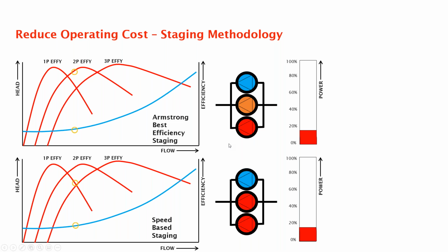And now we're going to click along, and you'll see the lower unit is actually increasing in power requirement, while the upper system is maintaining the same level of power while bringing the second pump online. That's amazing. We have the same result, but one of them is about 30% of total power capacity available for the pumps, and the other one is still around 18 to 20%. As we continue on in the speed versus efficiency staging, we'll come up to the next point where you can see now we've risen up to 40%, and we continue to go down the speed curve, and we're all the way out at 80% of that curve.